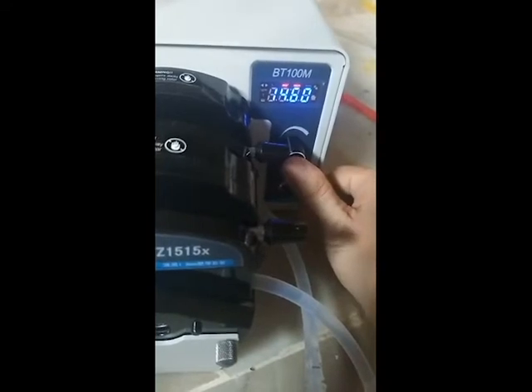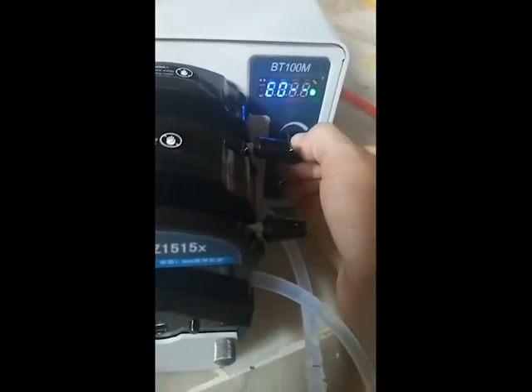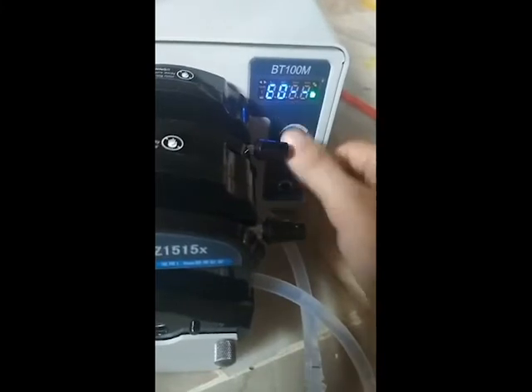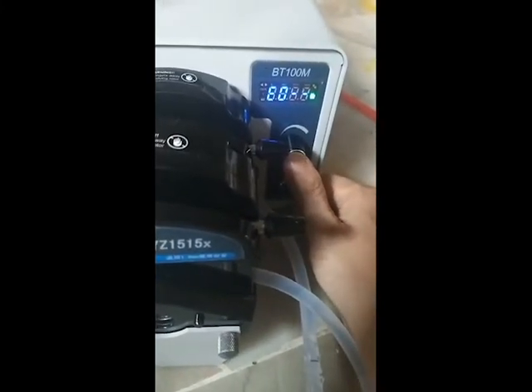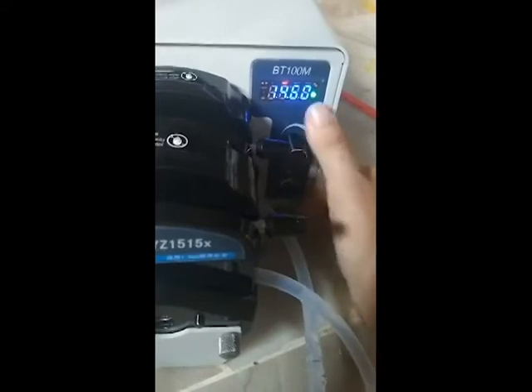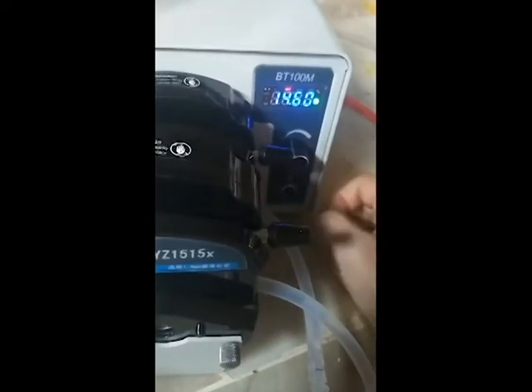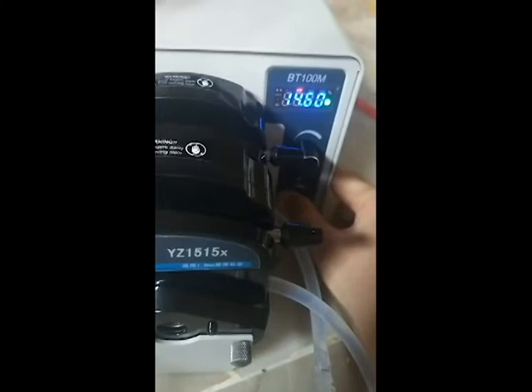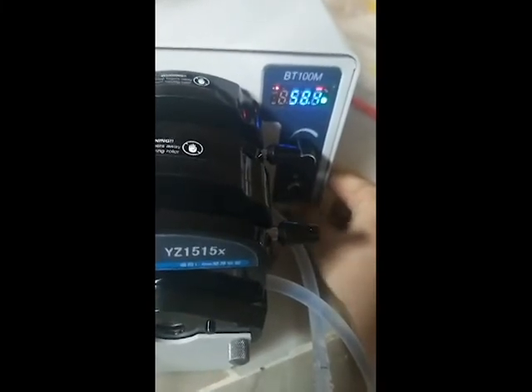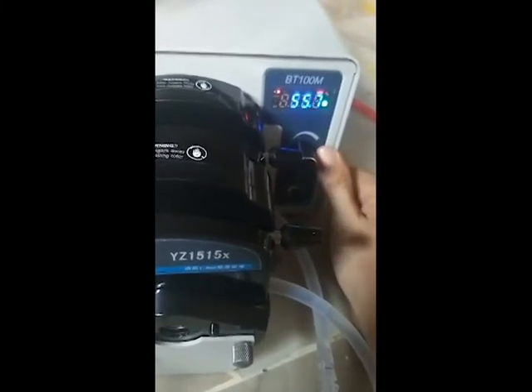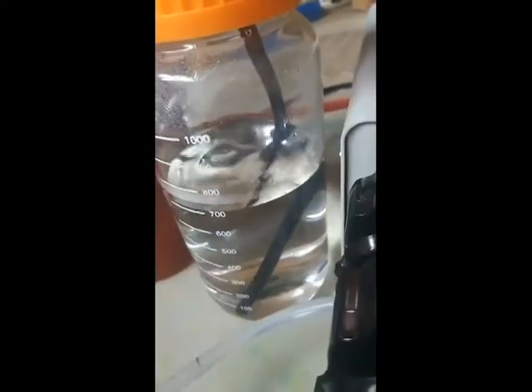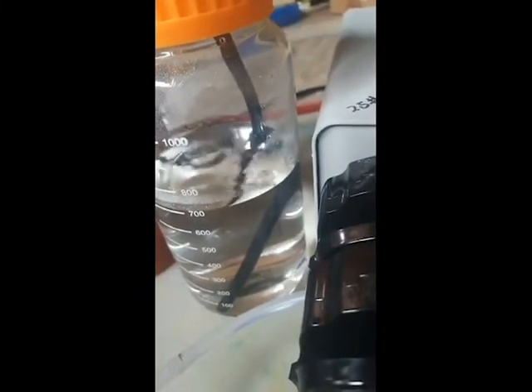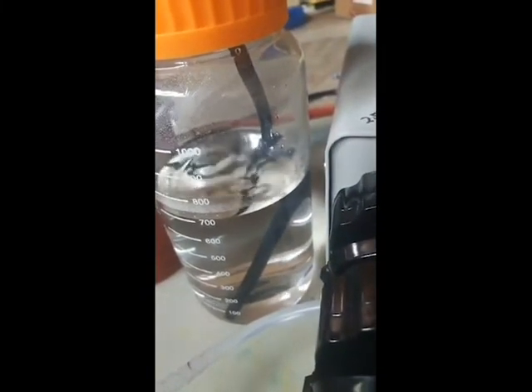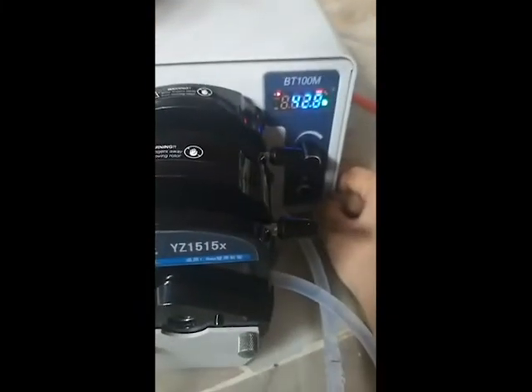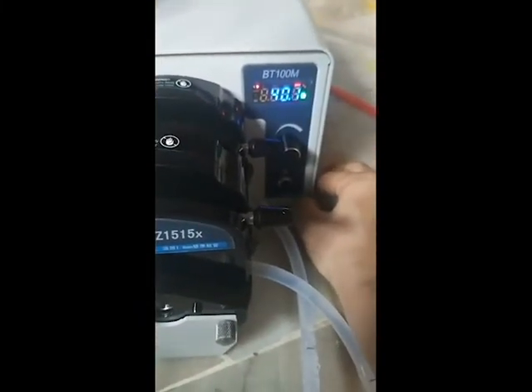At this moment, you click to choose E0 to enter the calibration, and click to confirm to enter the calibration. Then your calibrated value is 4.6. At this moment, you can turn on the pump. It starts counting time within 1 minute. During this 1 minute, the liquid needs to be all collected into one container, for example a testing tube or a beaker, because this liquid needs to be fully collected and used for calibration.